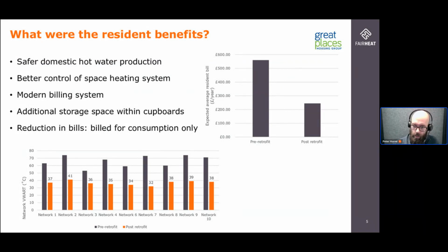So we put a plan in place for HIUs to be retrofitted, replacing those cylinders and changing the DHW, the hot water supply, from stored hot water to instantaneous, reducing fairly dangerous temperatures of around 65 to 70 degree hot water outlets down to 50, 55.